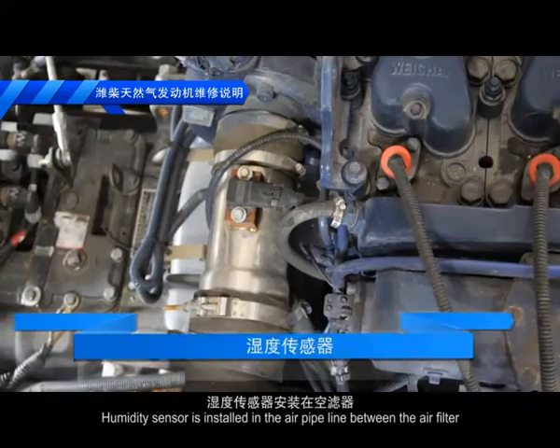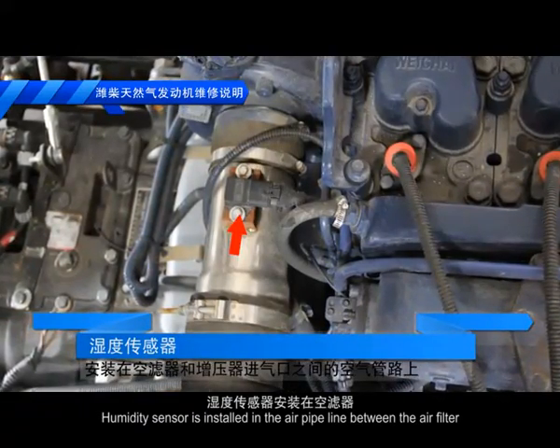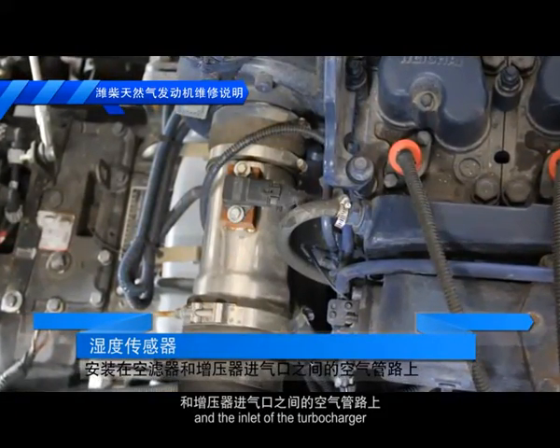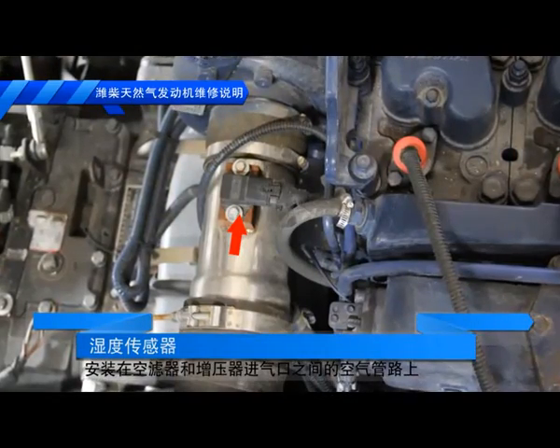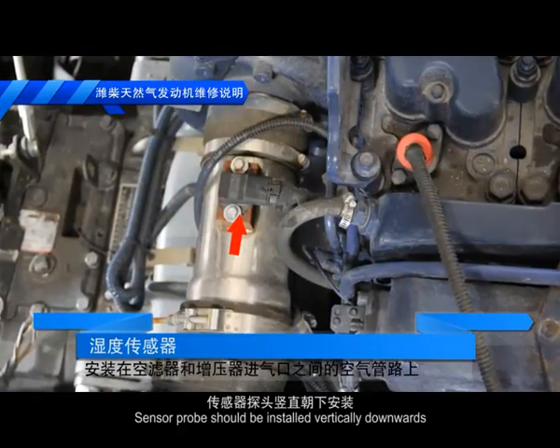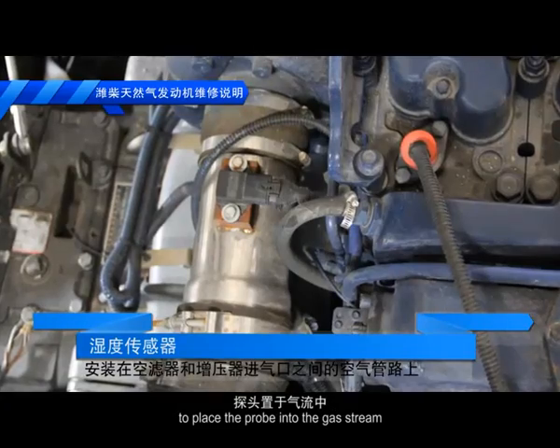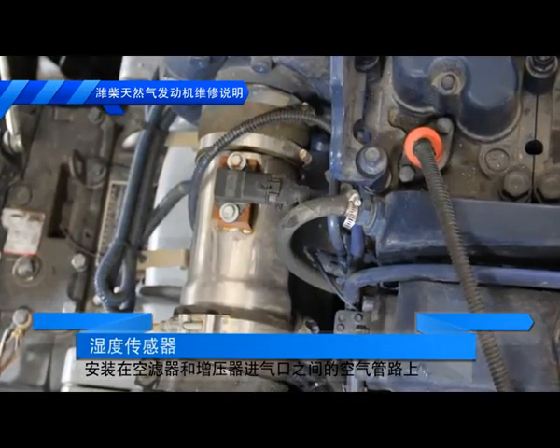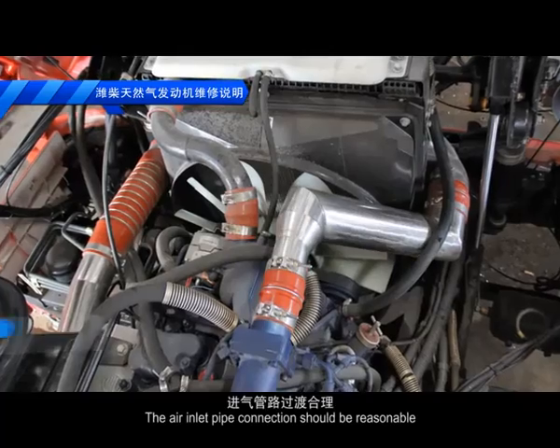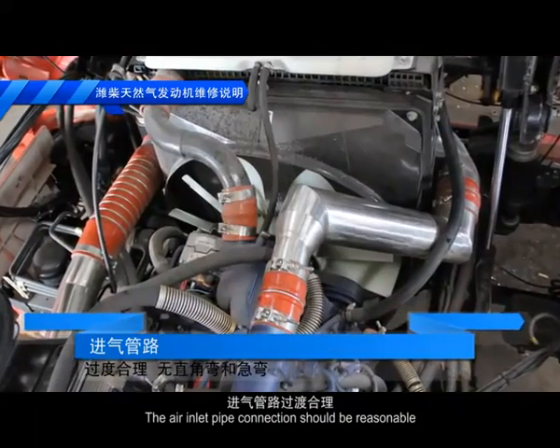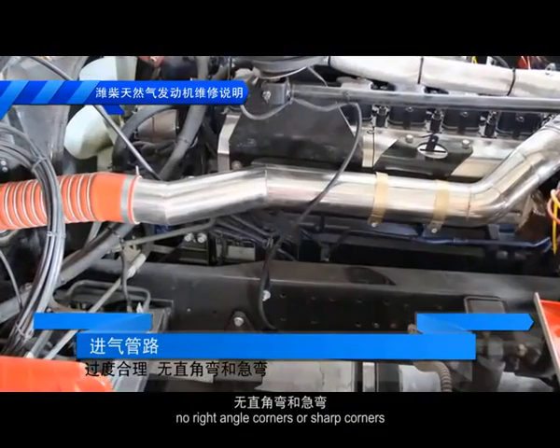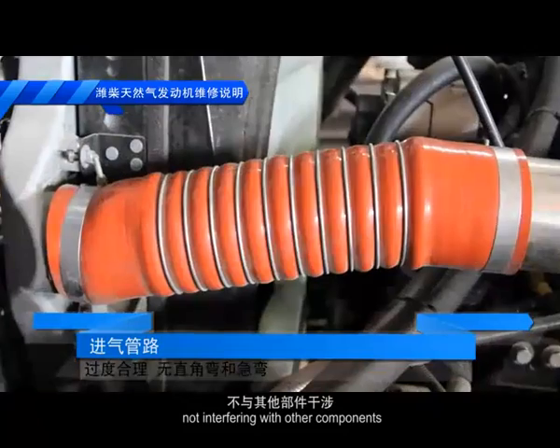Humidity sensor is installed in the air pipeline between the air filter and the inlet of the turbocharger. Sensor probe should be installed vertically downwards to place the probe into the gas stream. The air inlet pipe connection should be reasonable, with no right-angle corners or sharp corners, not interfering with other components.